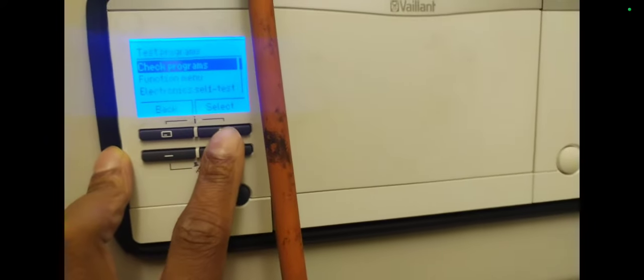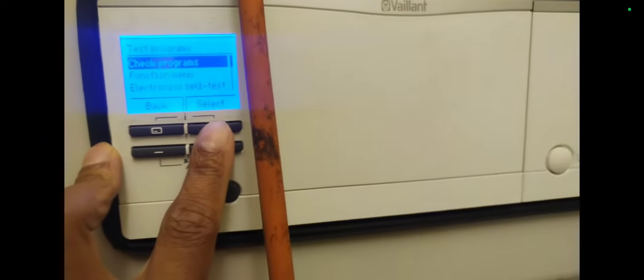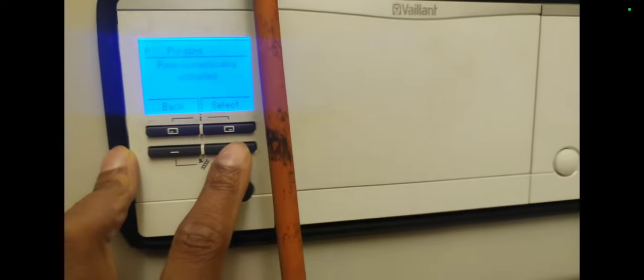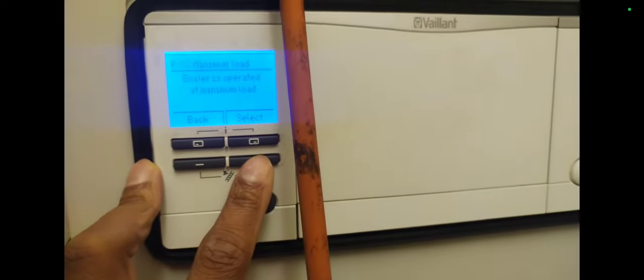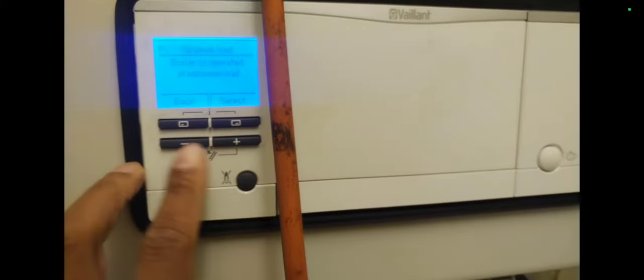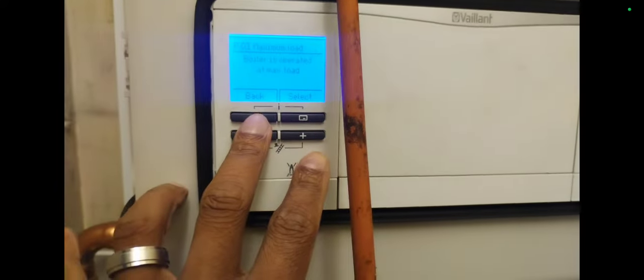Test programs. Check programs. It can be hard to remember all the different ways of getting boilers into high and low. Minimum load, maximum load. So high fire first, as always, and then low fire, and then maximum load. Do remember on boilers when you're doing servicing to put the boiler at its maximum, and remember to put all the settings back to how you found it.